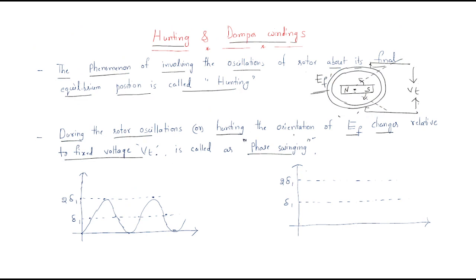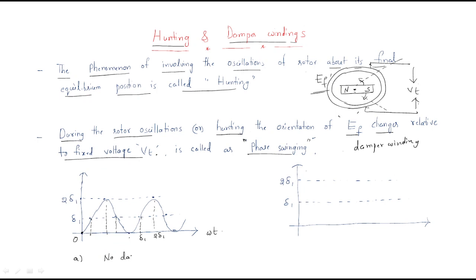To reduce hunting, we provide damper windings. If we don't have any damper winding — that means no damping — the load angle varies continuously: from 0 to δ1, then up to 2δ1, then back down to δ1, then to 0, and repeats. This is the case of no damping.